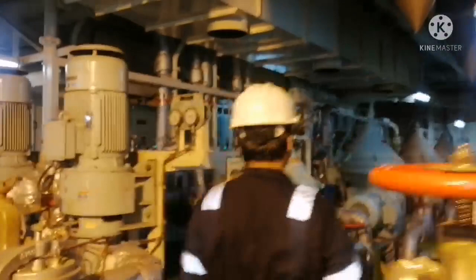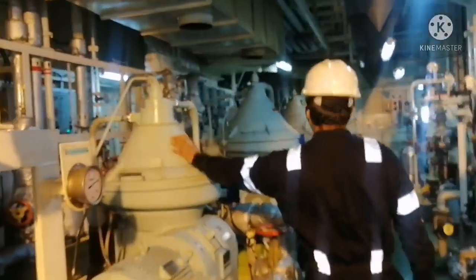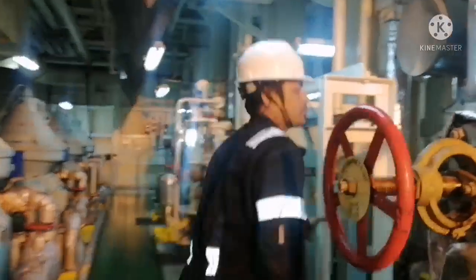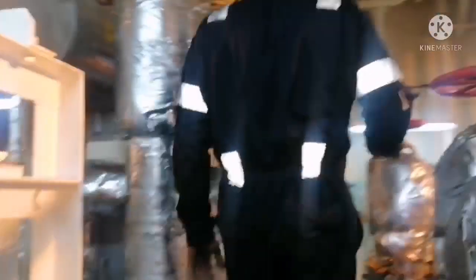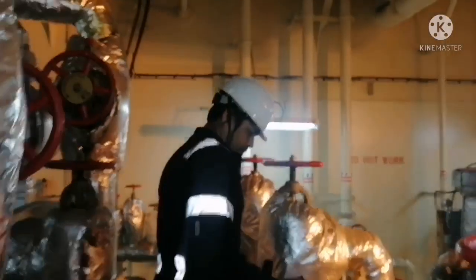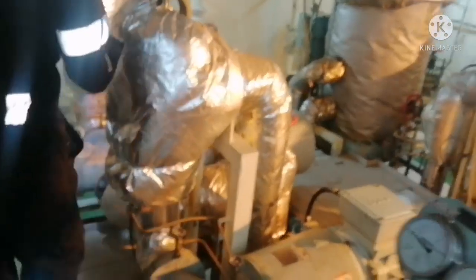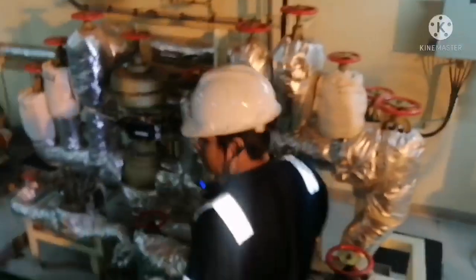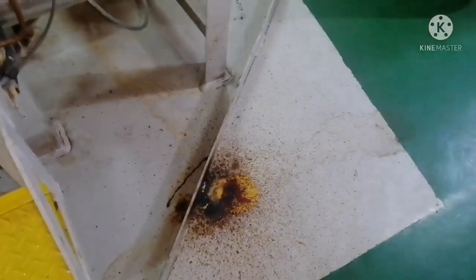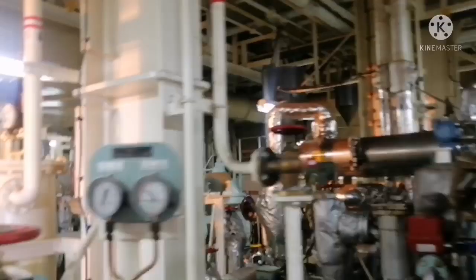So this is your fuel oil circulating pump, main engine fuel oil circulating pump, service pump. All purifiers will be here. You just check for the purifier parameters, just check for any leakages, any steam leakage, any fuel oil leakage, or any kind of abnormalities, any drop in pressure, any abnormal noise in motors, any abnormal noise in purifiers, and everything you have to check. Here I can find a small leakage, so this is not a big issue, but we have to attend to it. So we will tighten the gland so that there won't be any leakage.